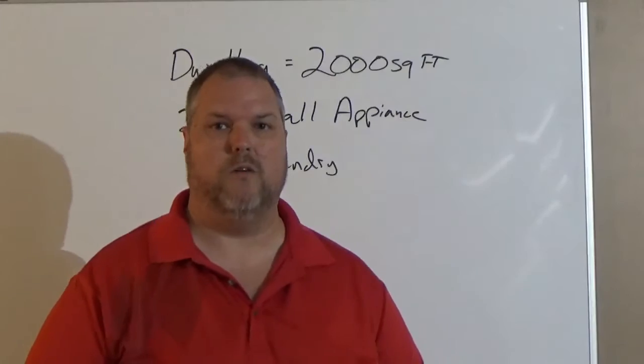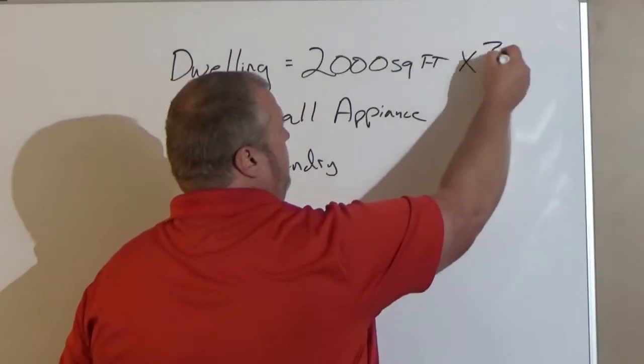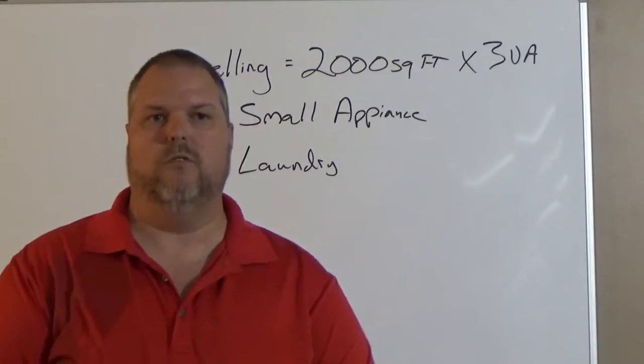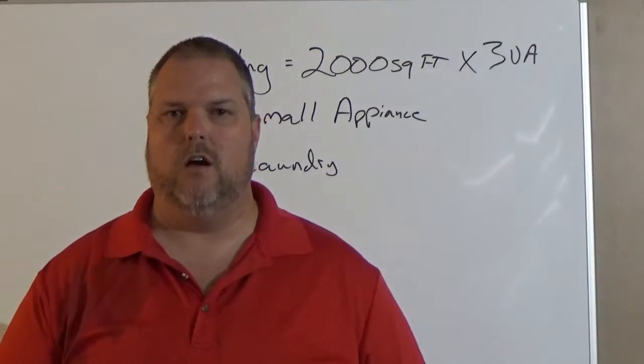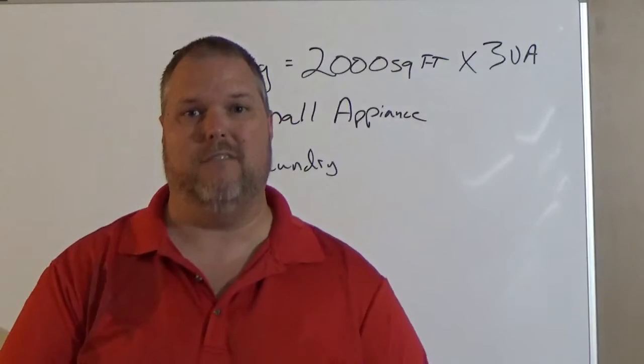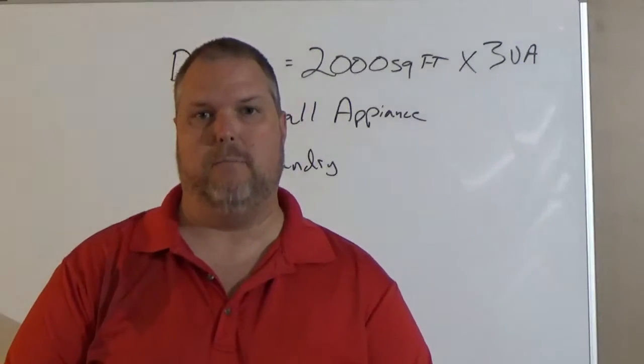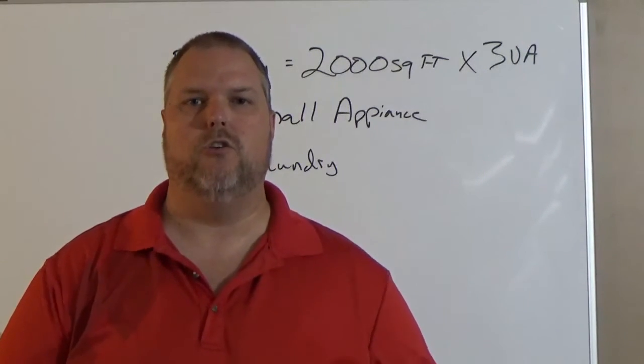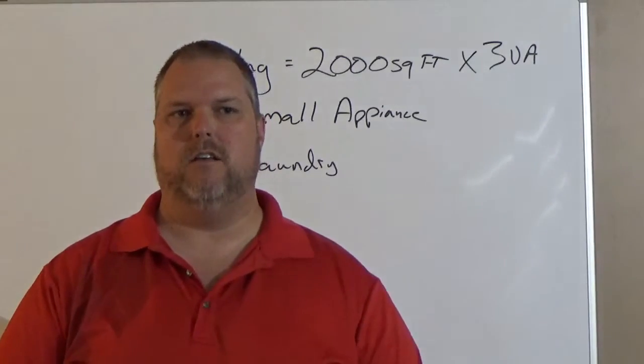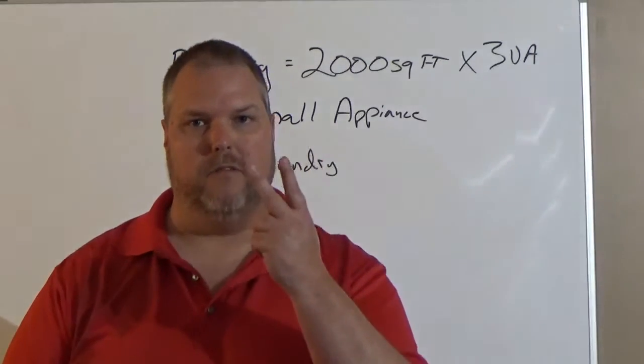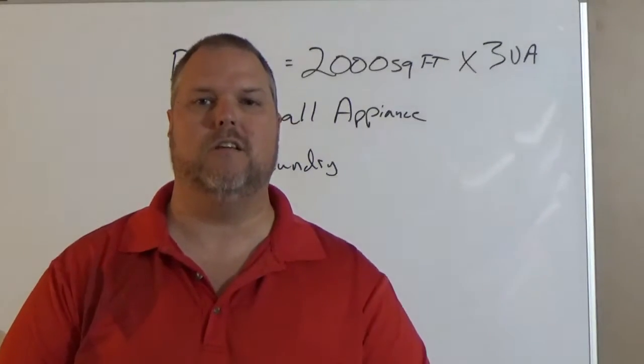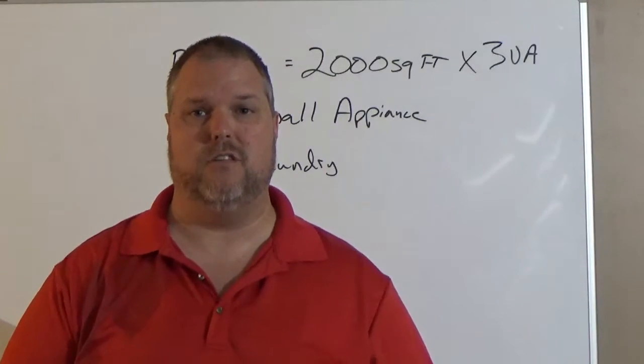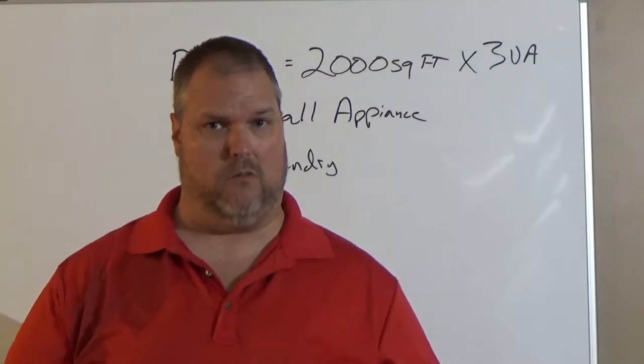We're going to take the 2,000 square feet and multiply it by 3 VA. Appliance circuits now, when we go into Article 220.52(A), that tells us we have to take 1,500 VA per branch circuit. According to 210.11(C)(1), you need to have a minimum of 2 branch circuits, right? So I'm going to take those 2 branch circuits, I'm going to take them 1,500 a piece. That's 3,000.